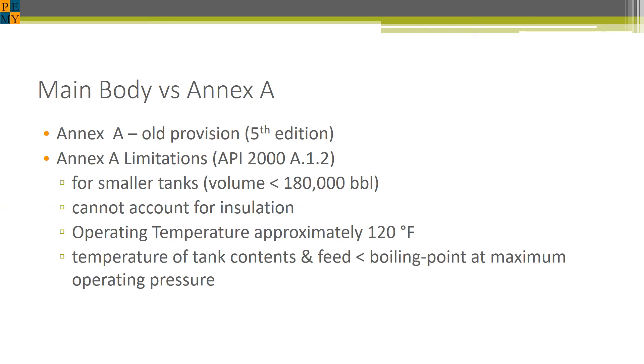Before I cover the details of the calculations, I want to first contrast the current main body or chapter 3 of API 2000 versus Annex A. Annex A used to be part of the main body back in the 5th edition. However, due to some recent research in vapor contraction and vapor generation, they found that in very rare circumstances, the old provision was actually unconservative. To alleviate this, they developed this new standard which is now in the main body and relegated those old provisions into Annex A.